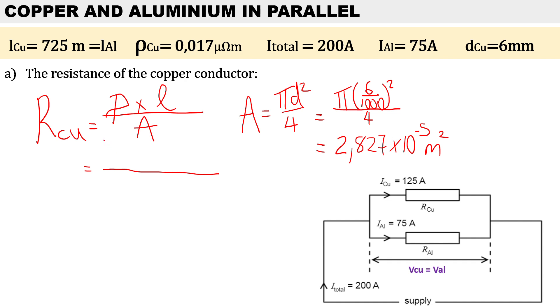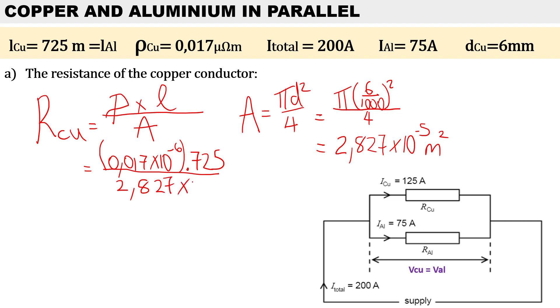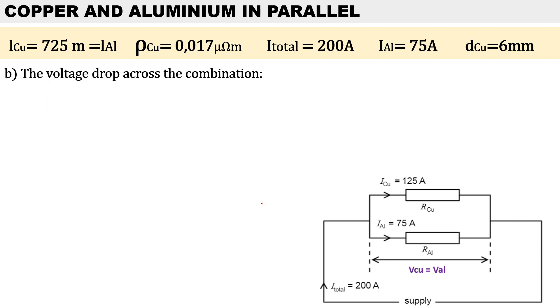Remember the resistivity must be in ohm-meters, so we multiply by 10 to the power of minus 6 to convert micro-ohm-meters to ohm-meters. The length is 725 meters and the area is 2.827 times 10 to the power of minus 5. Therefore the resistance for copper is 0.436 ohms.